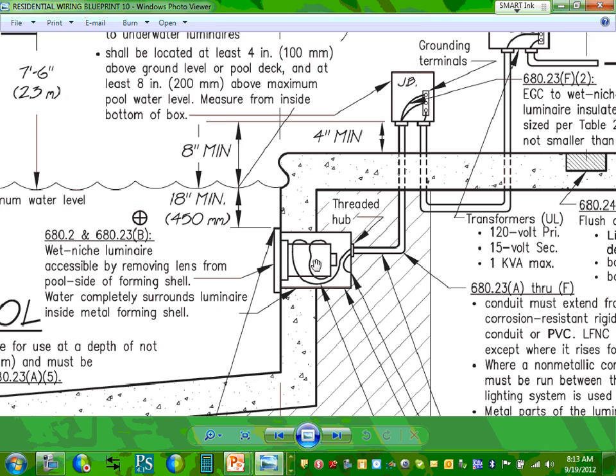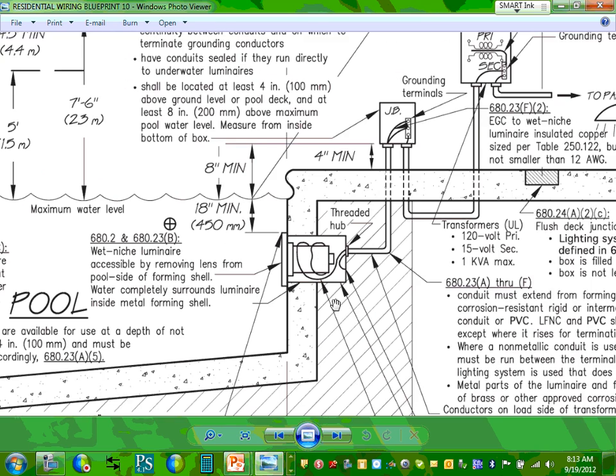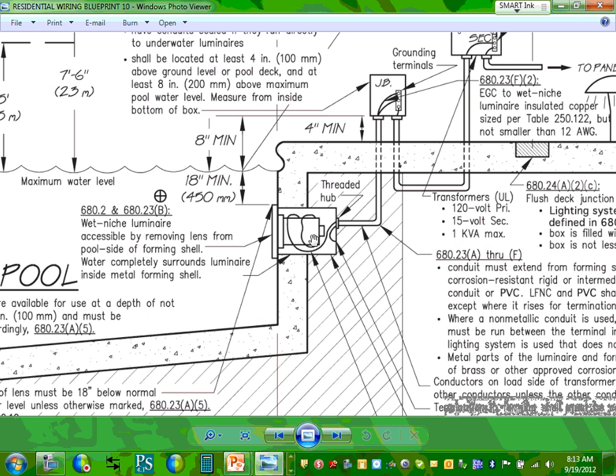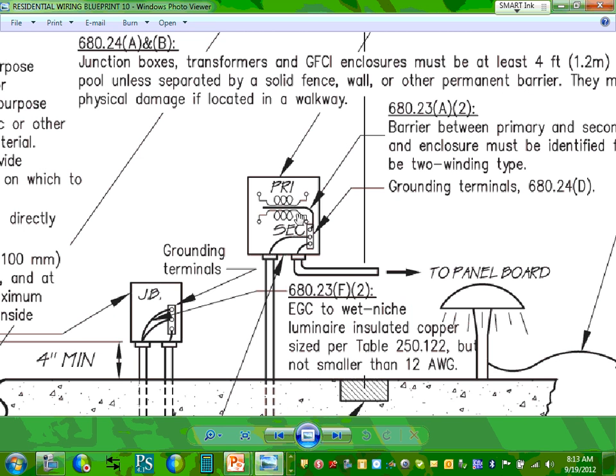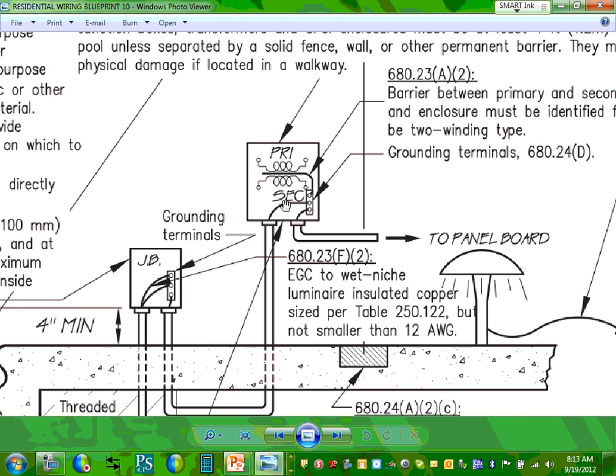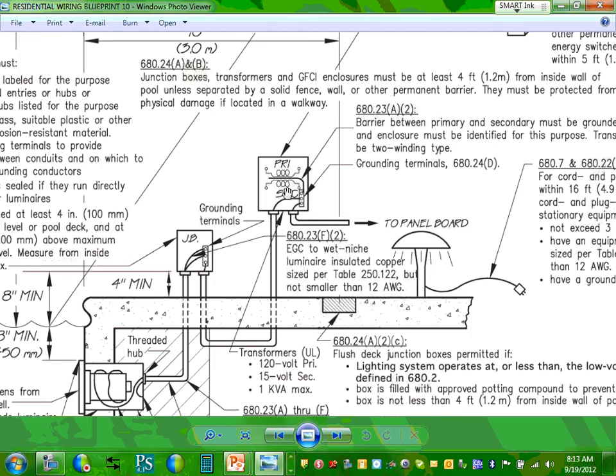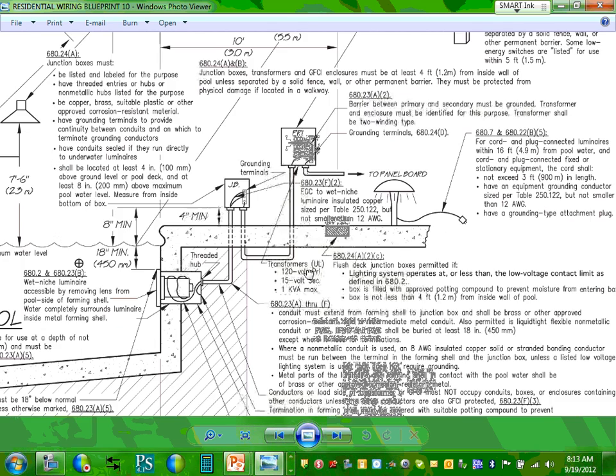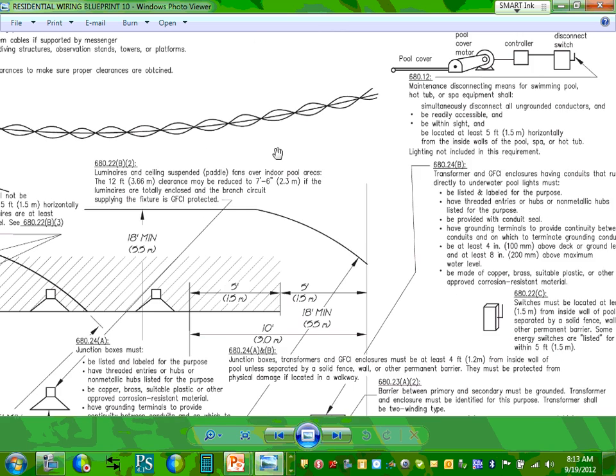Here's your wet niche luminaire and dry niche luminaire that we talked about, and the grounding. You need to have an isolating transformer. Do you guys remember we talked about this one with a number 12 conductor coming to it with PVC conduit? You have to, so that's for this.